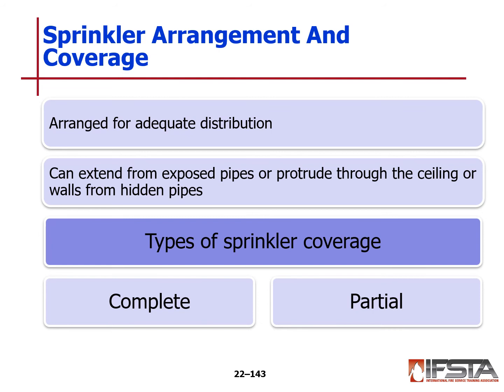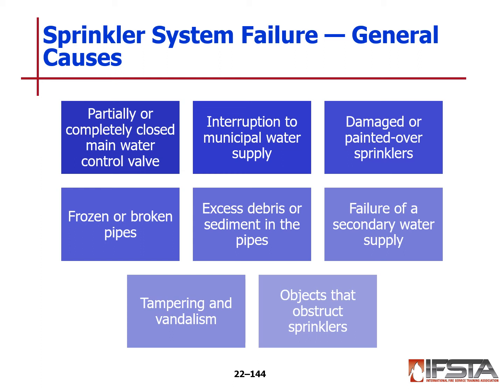Sprinkler arrangement and coverage usually are arranged for adequate distribution. They can extend from exposed pipes or protrude through the ceiling or walls from hidden pipes. There can be complete coverage or partial coverage. General causes of a system failure: partially or completely closed main water control valves. It's just like with anything, a partially closed or partially open valve does not allow all of the flow that valve should allow. That can cause you problems. Interruption to the water supply itself can cause a system failure. Damaged or painted over sprinklers and sprinkler heads can cause them not to work or function properly.